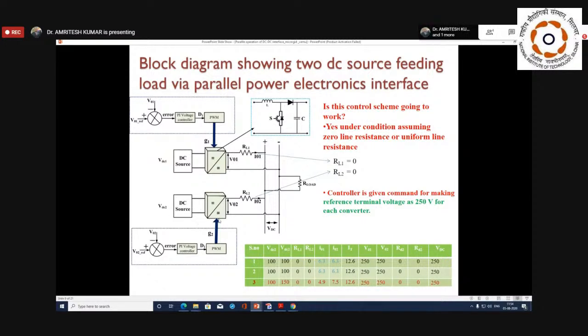So if VDC2 is of higher voltage or higher power rating, the VDC1 current will go down. It's getting down, even though it has the capability to transfer the current, but it is not able to do so because of this present control. So far it may work, there is no issue, but the problem with sharing will come when one source has a higher value or higher current rating.